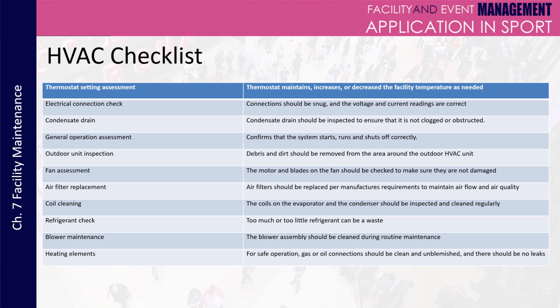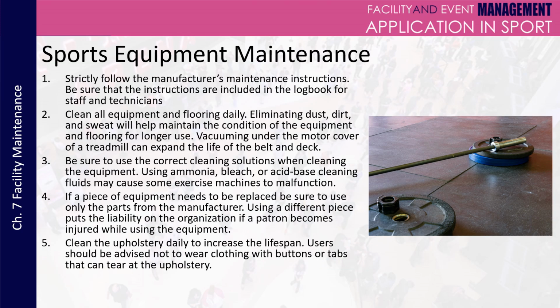You're also checking the electrical connections, to make sure that the connection is snug and the voltage and current readings are correct, that the system starts, runs, and shuts off correctly. The motor and blades on the fan should be checked to make sure they're not damaged. And the coils on the evaporator and the condenser should be inspected and cleaned regularly. You also want to do a refrigerant check to make sure that it doesn't have too much or too little refrigerant. And then the blower maintenance. The blower assembly should be cleaned during routine maintenance. And for safe operation, gas or oil connections should be clean and unblemished, and there should not be any leaks.